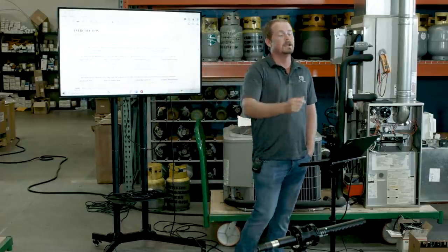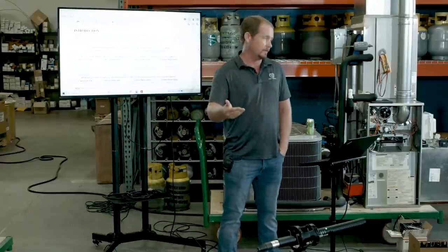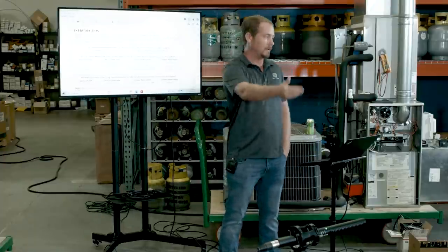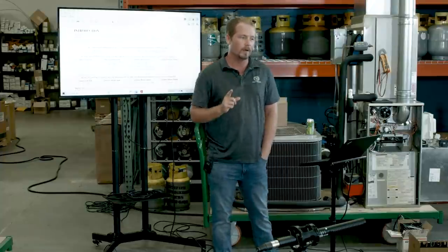So that can result in a flooded start, where you have liquid refrigerant that comes down out of the evaporator coil. So where do we want liquid refrigerant, or even we say liquid refrigerant because that's the primary mass. That's where most of the density is. Where do we want that refrigerant to be in the system when the system is off? The liquid line or condenser coil. Liquid line or condenser coil, right?